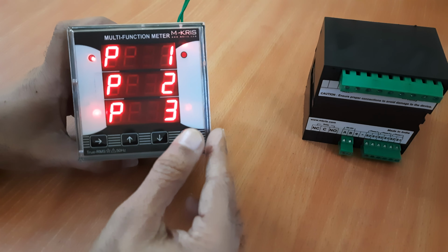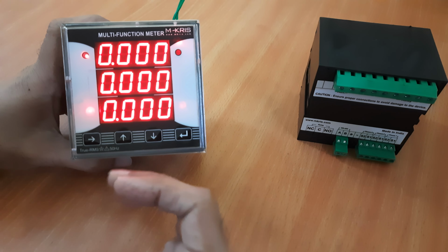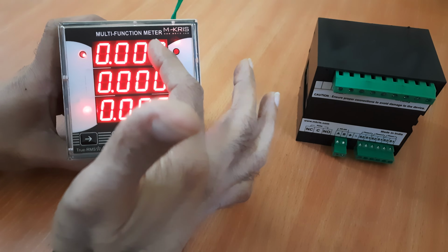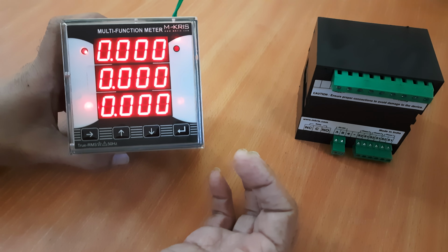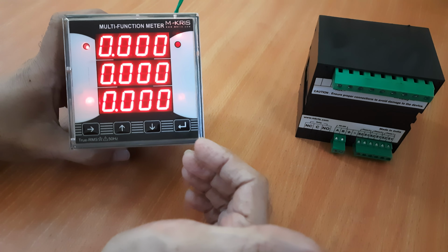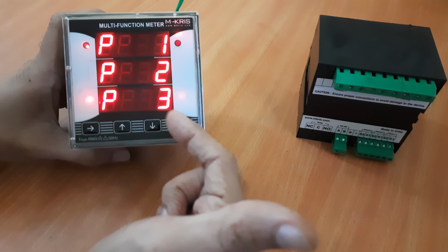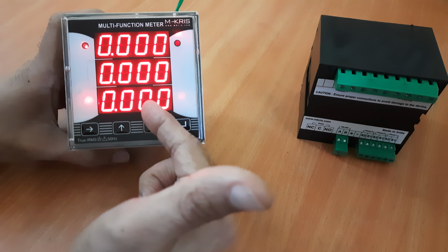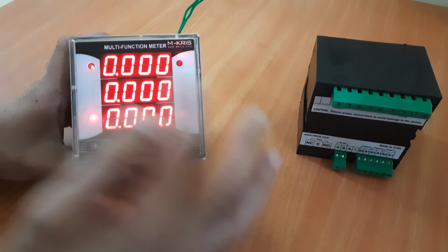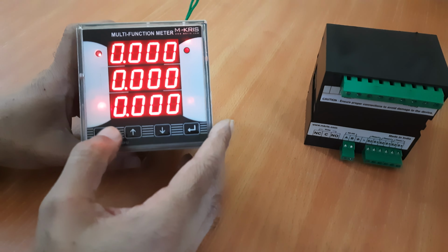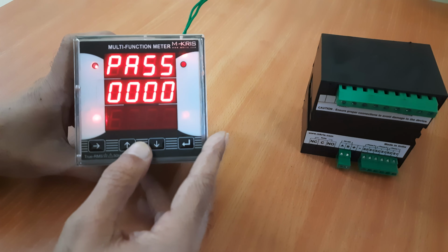Before we go into menu selection, let us understand that this reverse power relay acts when power in either of the phases goes beyond the export power setting or falls below the import power setting. So let us be clear that the tripping will be dependent on individual power, not on the total power. We'll have a small discussion when we make the settings again on this topic. So let's move to settings.